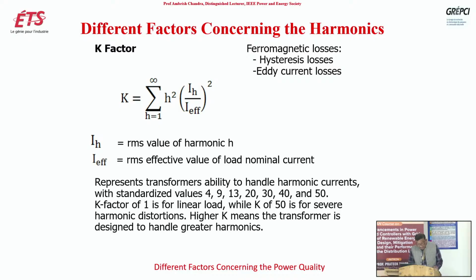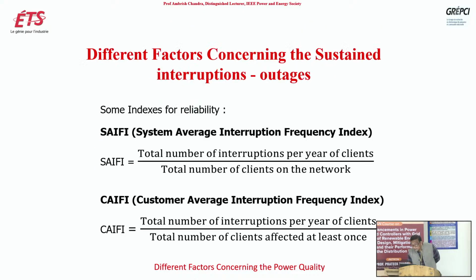Now there are other factors, like different factors concerning the sustained interruptions, outages. Outages means you have long-term outages. When we say outages, it may be in hours perhaps, you don't know. So some indexes, one is SAIFI. This index is basically used by managers to manage the system. As an engineer you will not be using it, but if you are a manager of a certain utility or certain area, you should be concerned about this. So SAIFI is System Average Interruption Frequency Index.